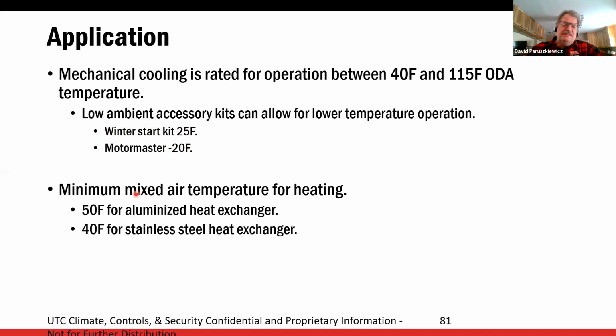Mixed air. These units are not designed as makeup air units. They've been installed this way forever, and you get all kinds of problems with them. The aluminized heat exchangers, which are the most common, are good for 50-degree return air. The stainless steel heat exchangers are only good for 40. By makeup air, I mean a makeup air unit that is 100% outside air. These units are not designed for that, and if you do use them that way, you're going to have all kinds of problems with condensation and cracking heat exchangers. Guys like to do it because it's a cheap alternative to a makeup air unit, but they're not designed for that, so we don't want to do that.